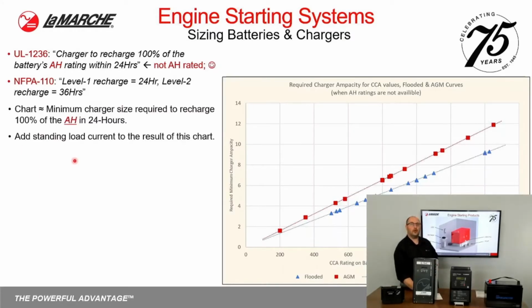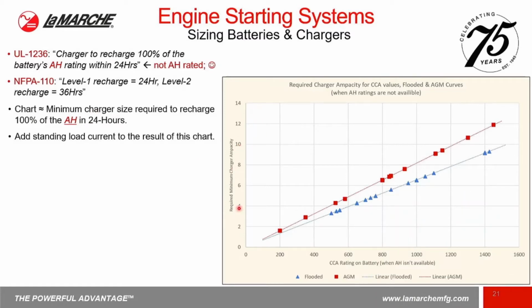So working with the IEEE, there's a chart that we can make here that correlates the minimum charger size in amps on the left column versus the cold cranking amp rating on the right. And it's not a direct perfect correlation. This is just one of those tables that was assembled from some available tests on a lot of available batteries. So if you have a standing load, you should add that to the result here.